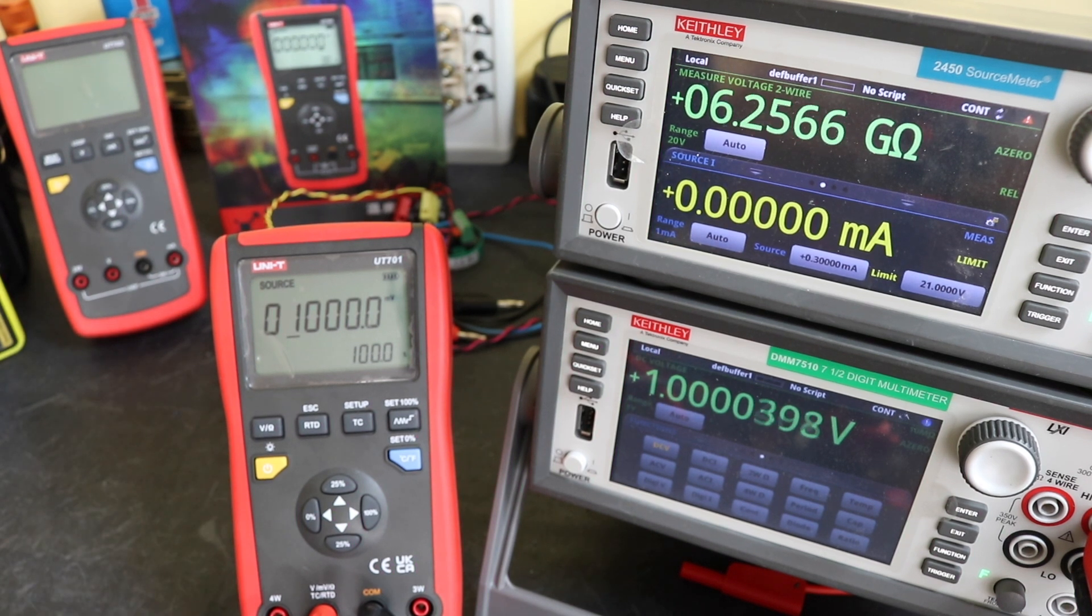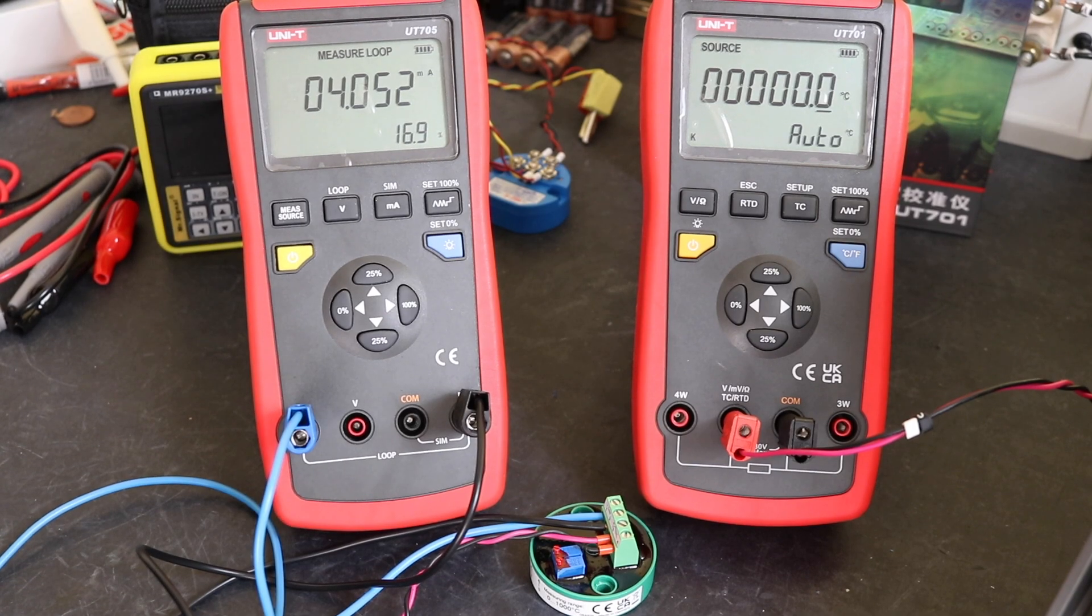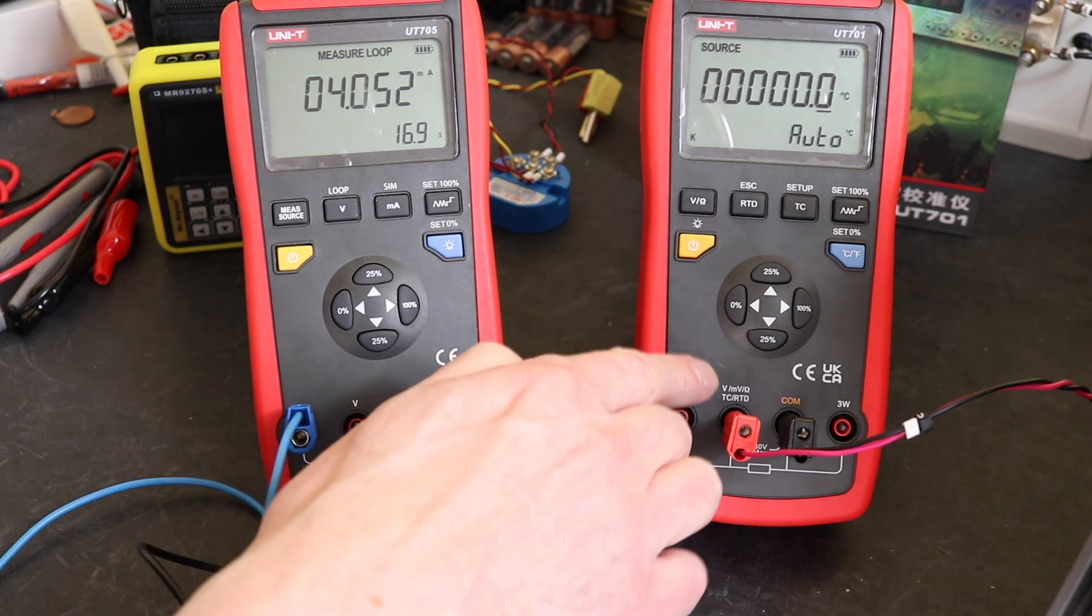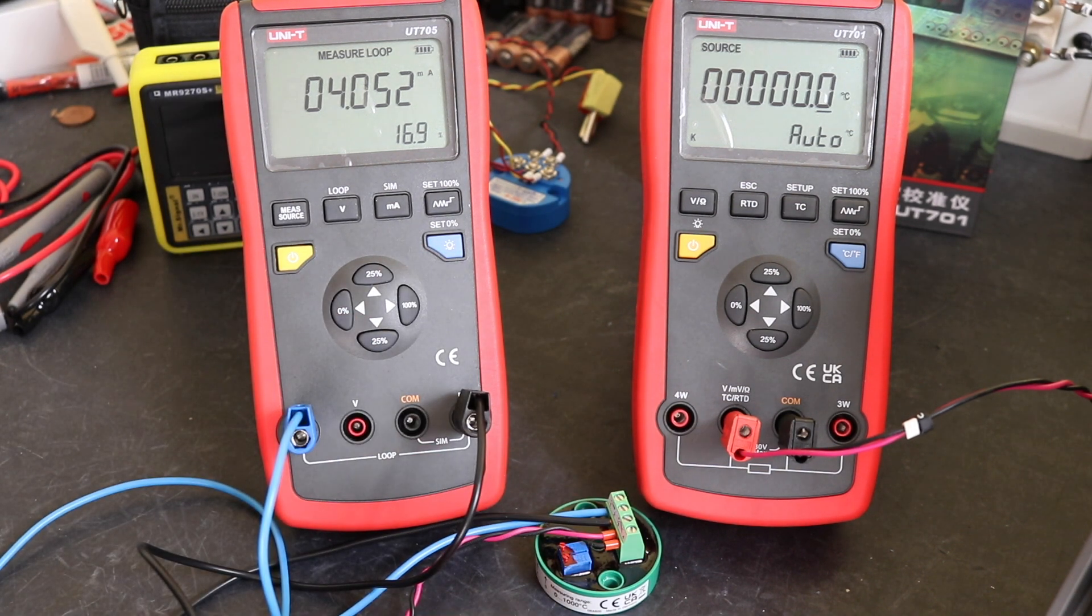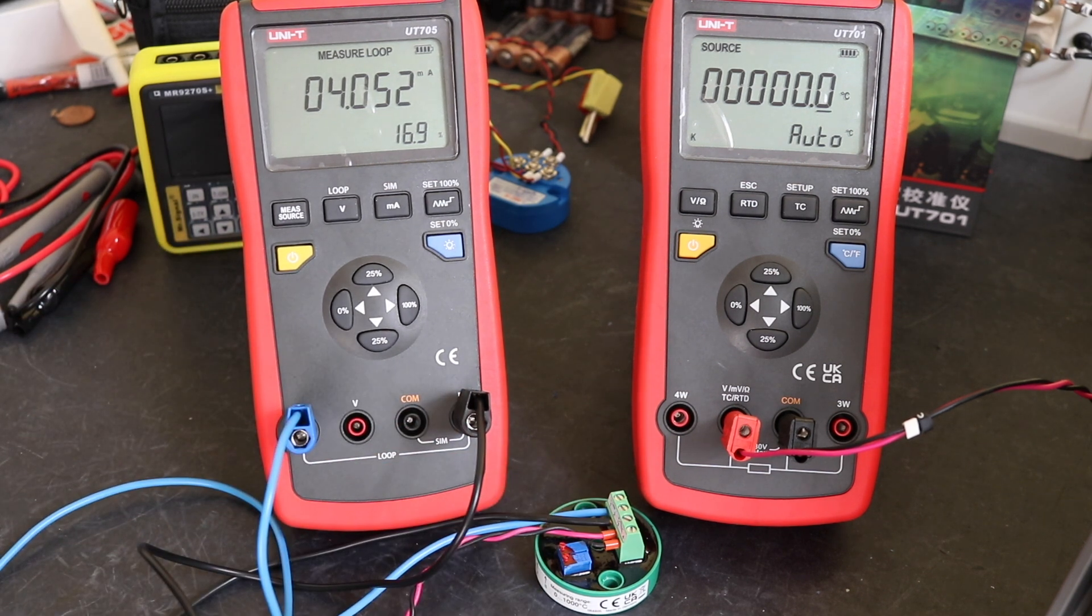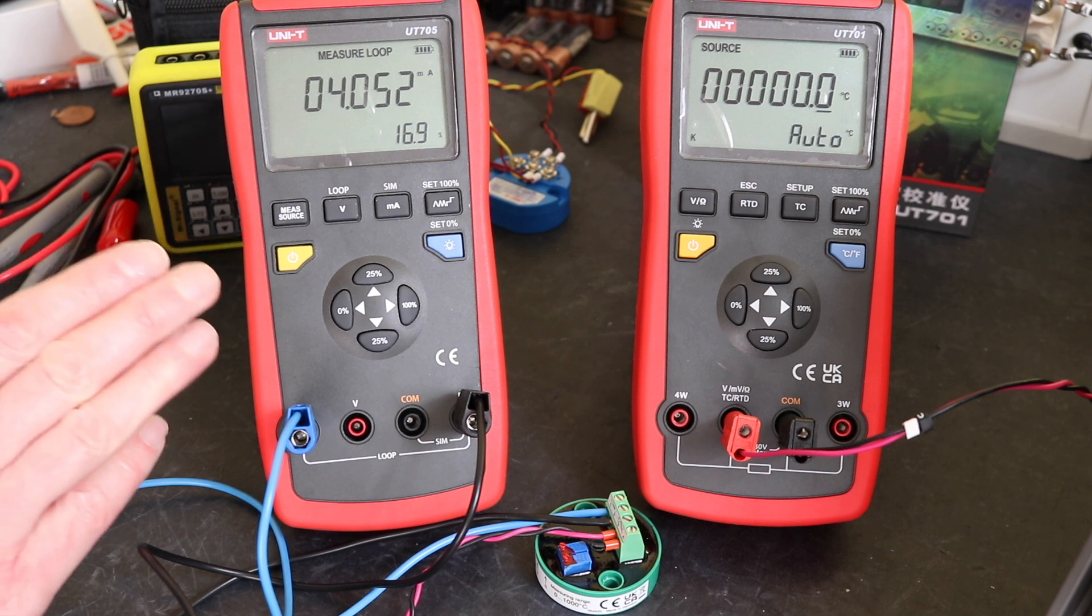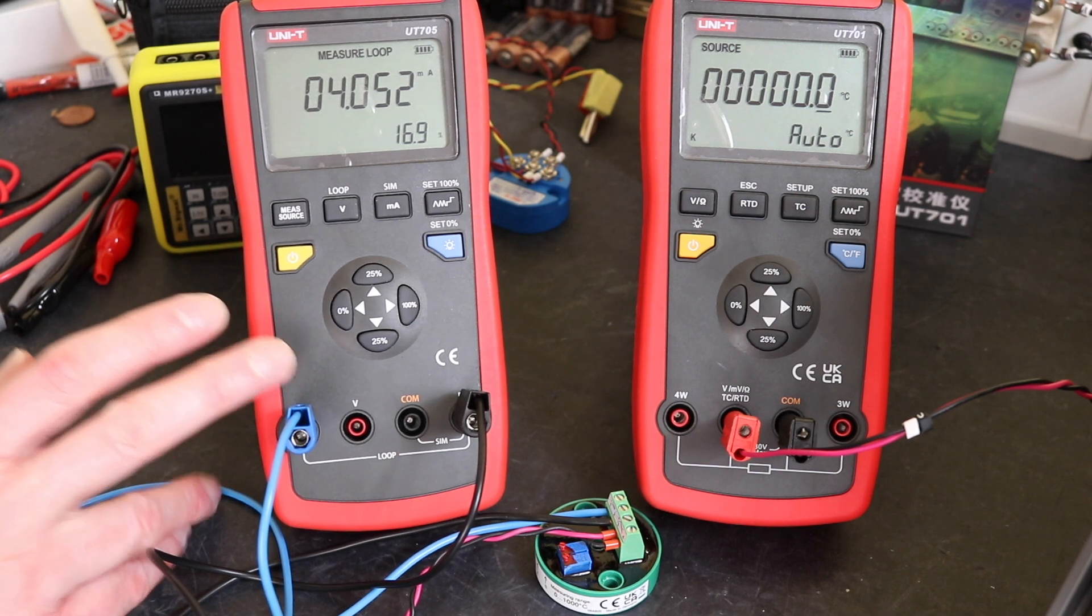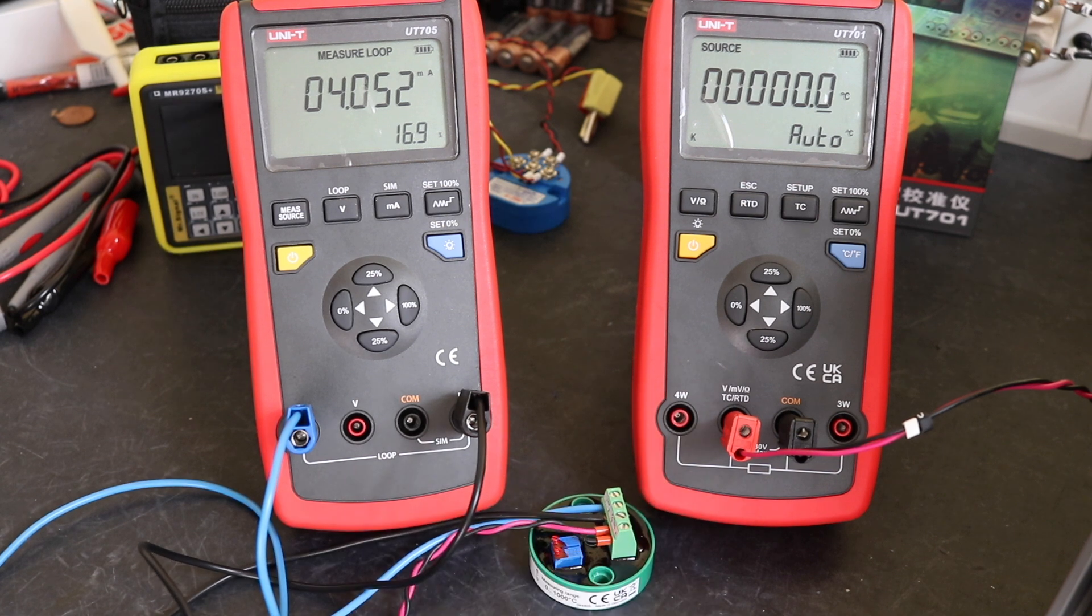So we've set our little transmitter up here. This is a K-type transmitter 0 to 1000 degrees range. So it matches the current settings up on our 701 here. We are using the 705 to measure the loop current and supply the 24 volts that is needed to power this. And we are reading 4.052 milliamps here. A little bit out at this bottom end. That could be this unit. It could be the UT701. I'm introducing another issue into the accuracy equation here. So just to be careful with that. But when I do test this with my reference kit, there's only about 0.02 percent in accuracy on our transmitter. So that's all fine.